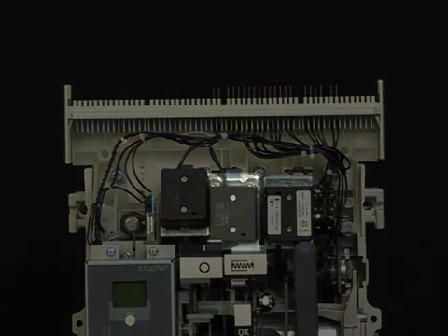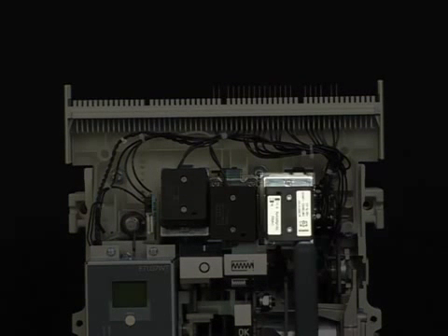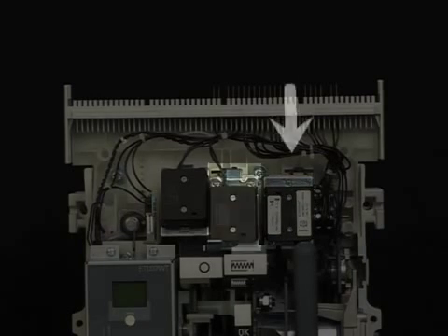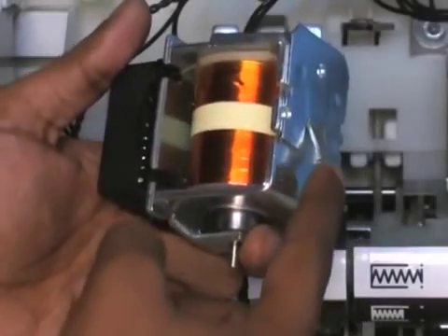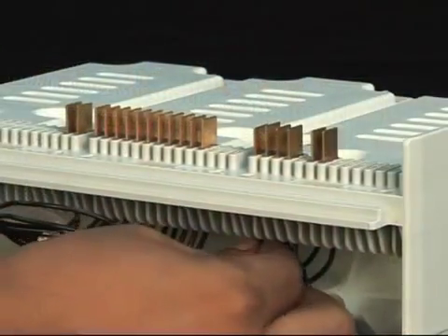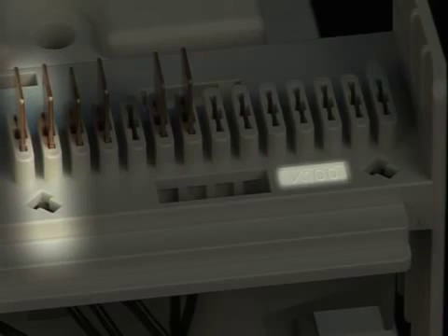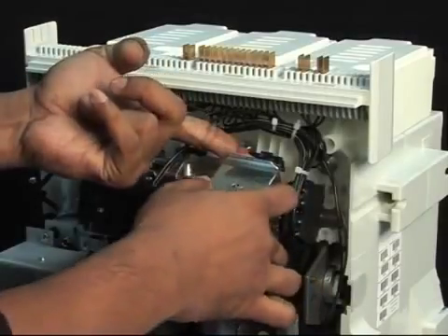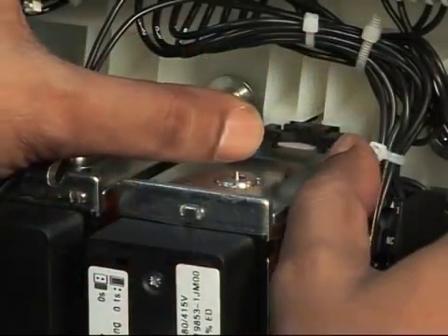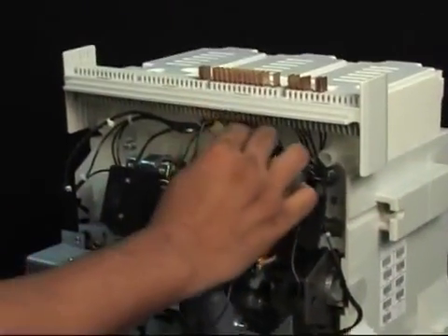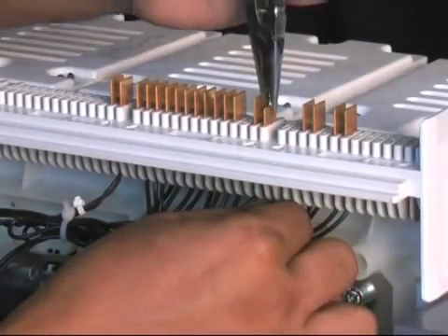The next slot is for the second shunt release, because the third slot would be occupied by the under voltage release. If there is no under voltage coil, you have to fix the shunt release in the third slot only. Please follow the similar process of fitting the bracket at the back of the coil into the groove. Once the shunt release is fitted, the wires are connected through the blade contacts to the auxiliary terminals X113 and X114. Now, the third slot on the extreme right gets fitted with the under voltage coil following the same process, and the blade contacts of the wires get connected to the auxiliary terminals X202 and X201.